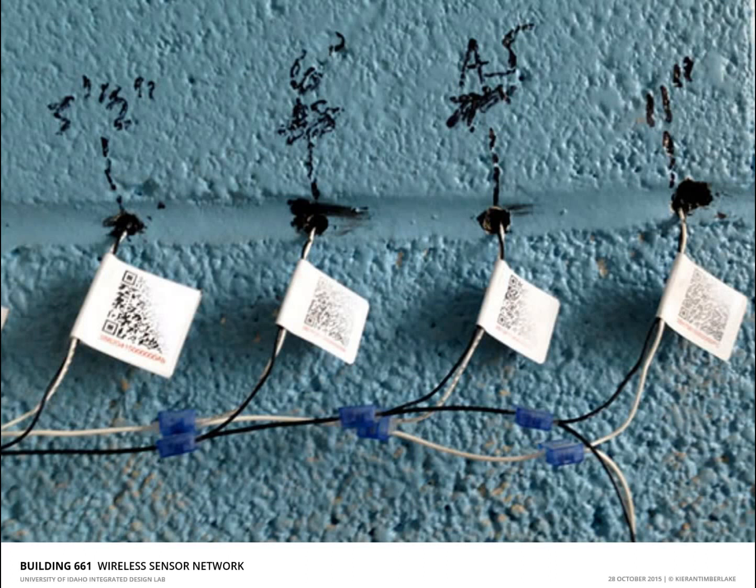Because otherwise, all you're left with is a bunch of spreadsheets, and you have no idea where all this information is coming from. So we devised a system that basically used the one-wire protocol, where every data point actually comes with a completely unique serial number from the manufacturer. So every time this piece of data would get pulled and go to our database, it would not only provide you a temperature or relative humidity reading, but would also provide a serial number. And that serial number could be associated with one of those tags, and it can also be associated with a name and a location in a model.